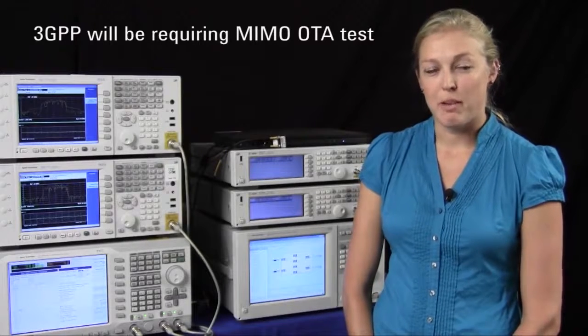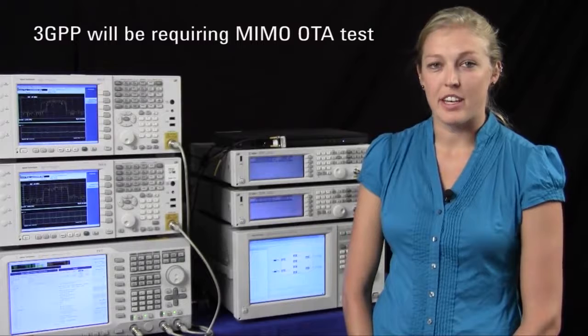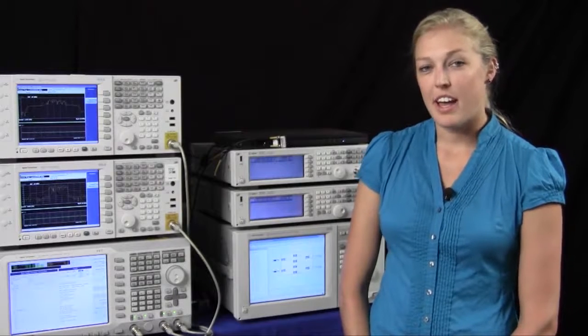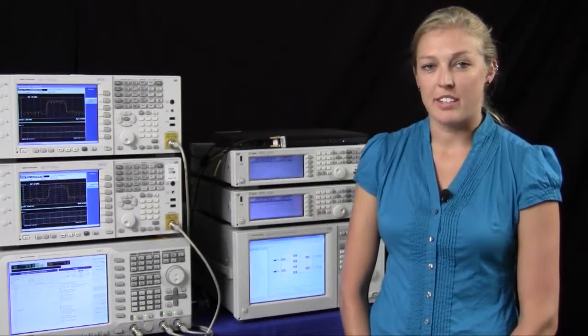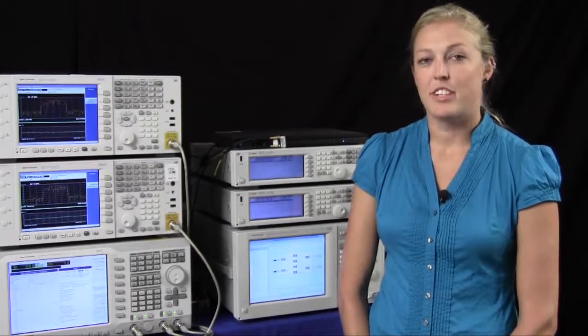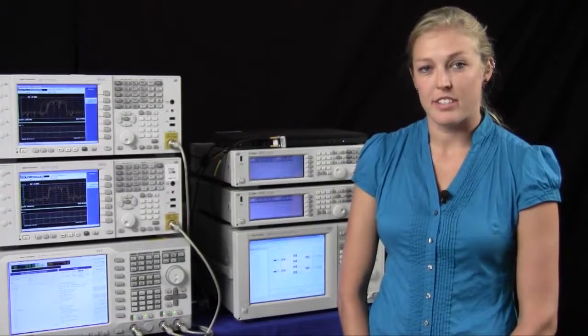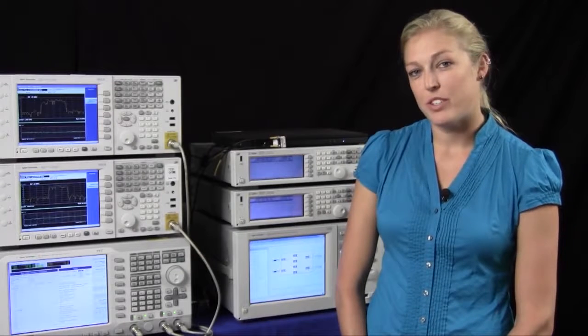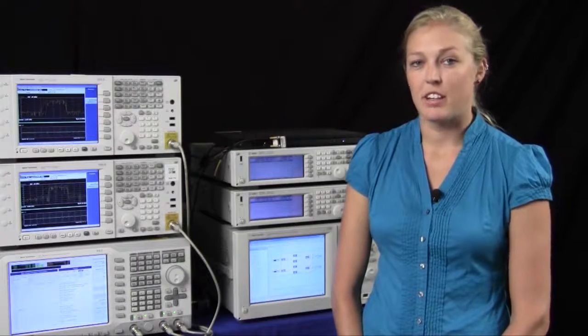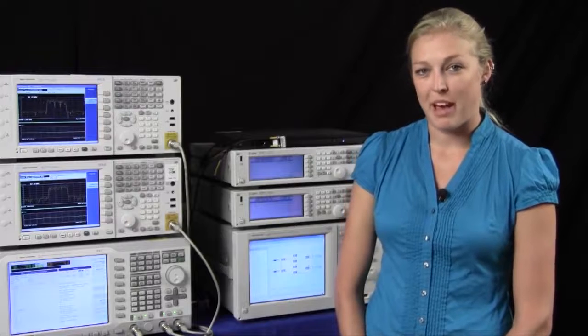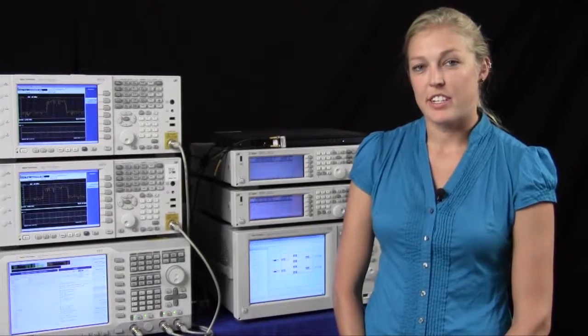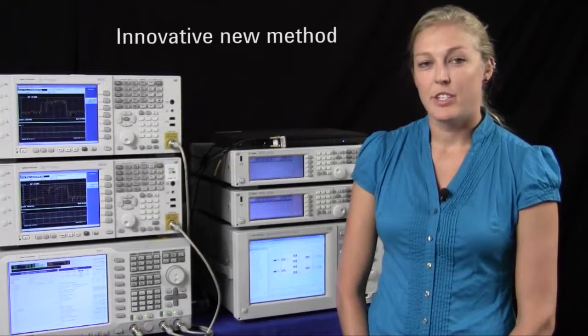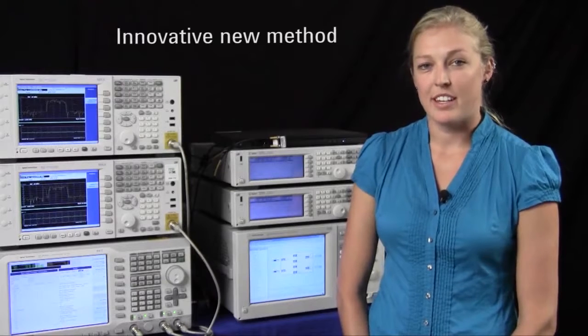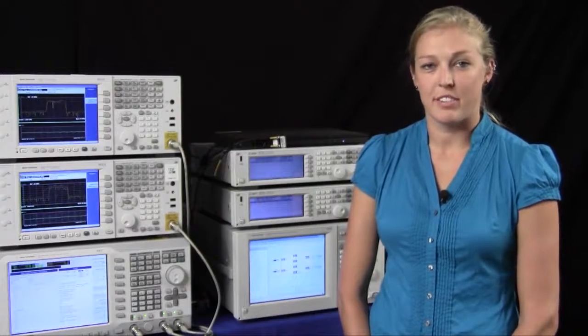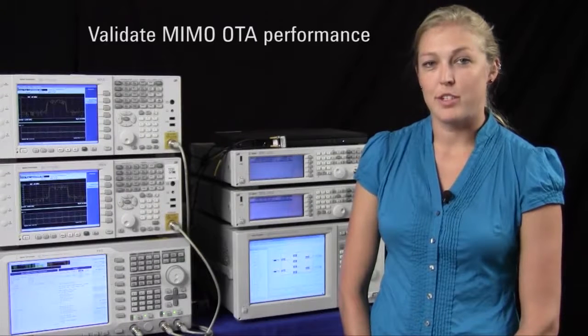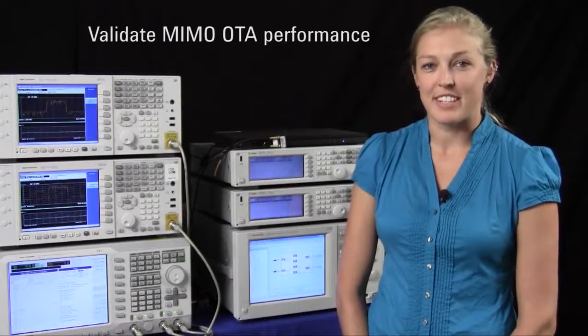3GPP will be requiring MIMO OTA test as part of their LTE conformance standards. CTIA and 3GPP are currently discussing what those standards will be, and Agilent is actively participating in those discussions. The ultimate goal of MIMO OTA test is to be able to distinguish a good handset or device from a bad one. Agilent's engineers have come up with an innovative new method to help LTE antenna and device designers quickly and cost-effectively validate the MIMO over-the-air performance of their LTE devices.